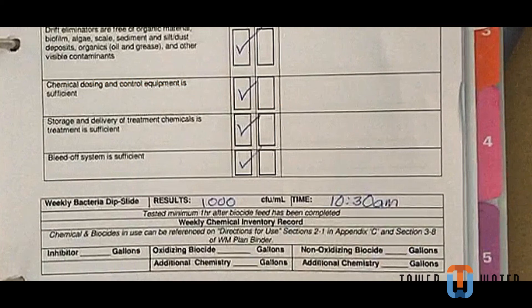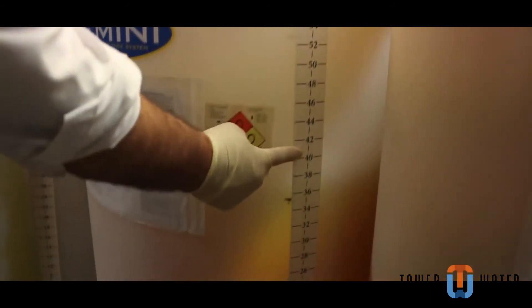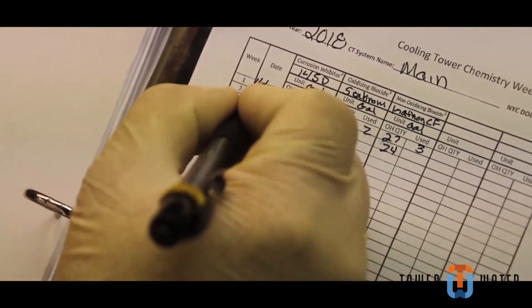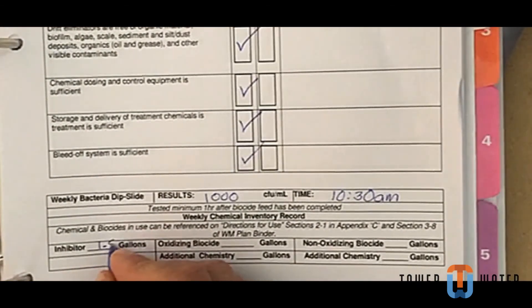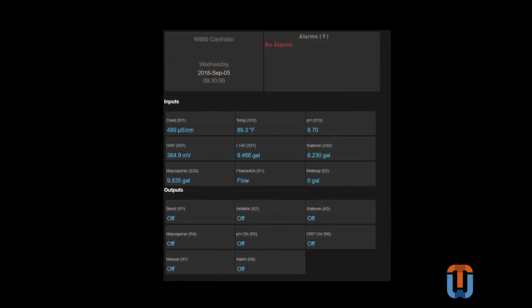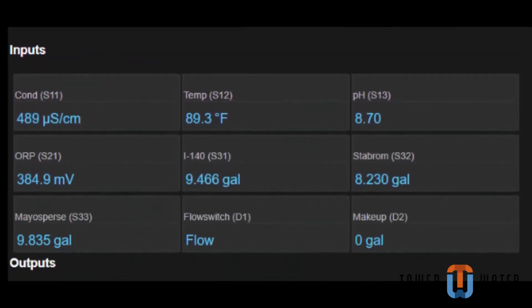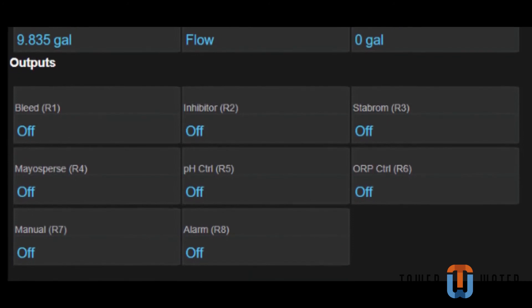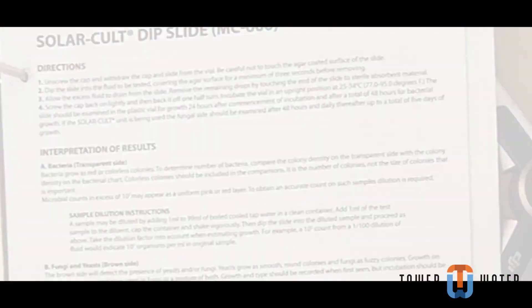There are two methods of gathering inventory. The first is accomplished by shining a flashlight on top of the container and looking on the side to see where the light hits the chemical level. Match the chemical level to the volume number strip on the drum, then subtract this week's level from last week's and record the difference as amount used on the checklist for each drum. If you maintain a smart controller with communications, you can receive a daily email with chemical levels for all drums. Retrieve the email from 7 days ago, compare it to this week's email, subtract this week's from last week's, and record the difference as amount used.